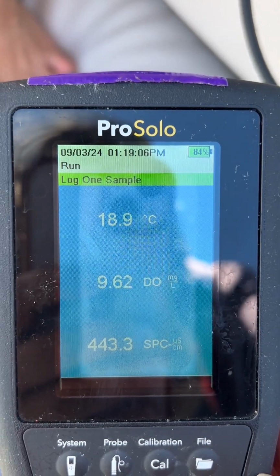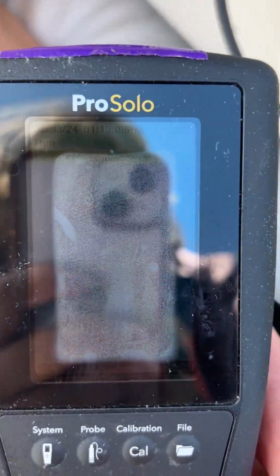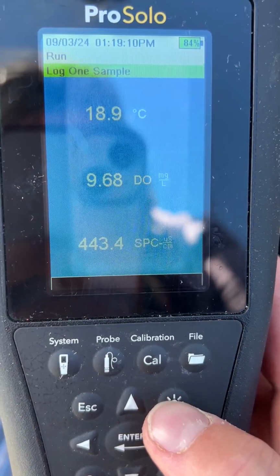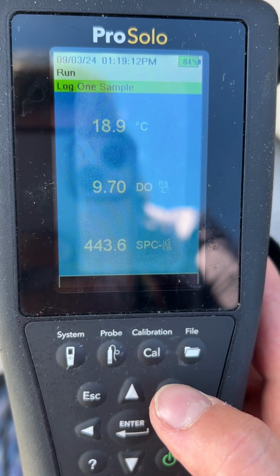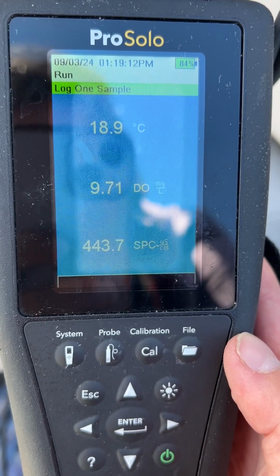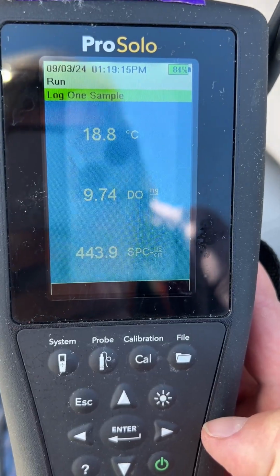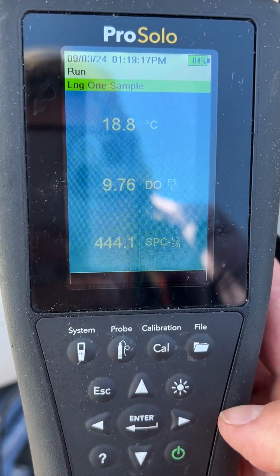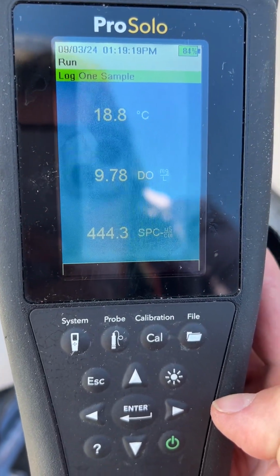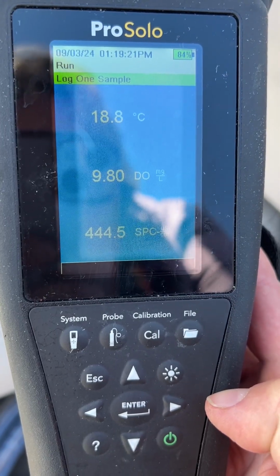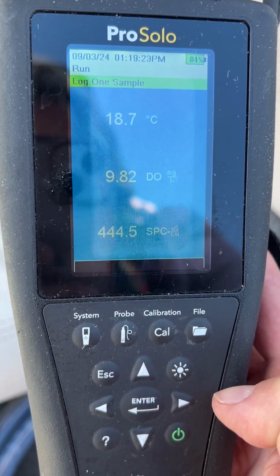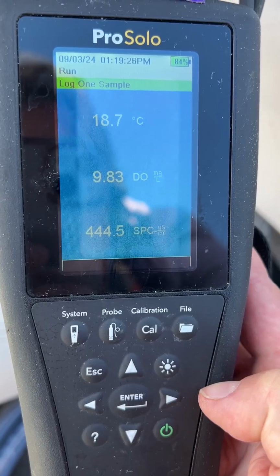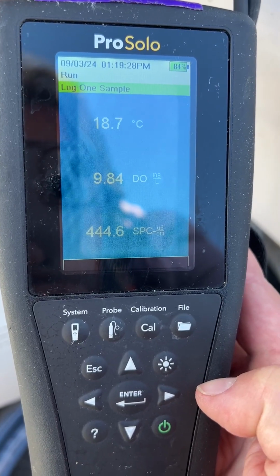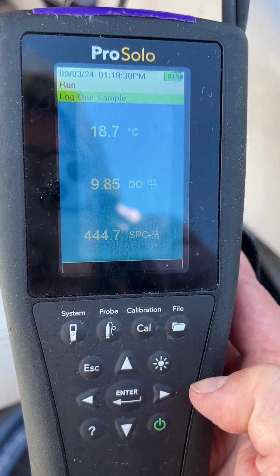We will go to our handheld, and on our main screen will be our readings. When you first put it in the water, wait a couple minutes for the values to stabilize and stop rapidly changing. It's likely the DO will never stop moving completely, so wait till it has slowed down significantly and use your judgment to record the reading on your field sheet. Once your numbers have stabilized, we can jot down the values that we are reading at that point.